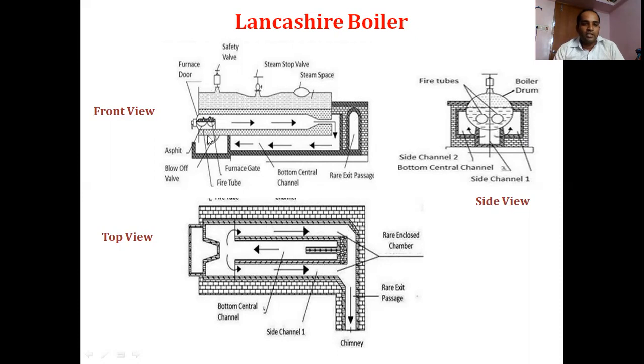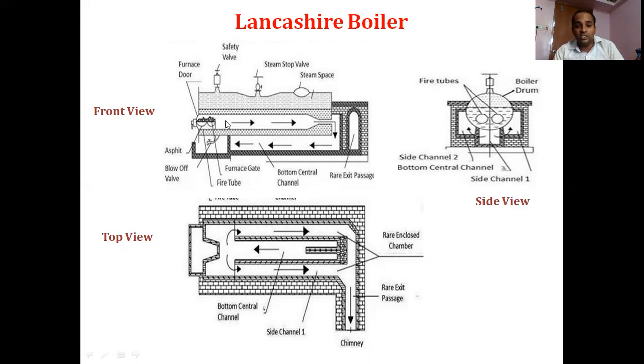Regarding the working of the Lancashire Boiler — it is a stationary boiler. It has two tubes, and within these tubes hot gases are circulated. So it is a fire tube boiler, where hot gases pass through the tubes and transfer their heat to the water present outside the tubes. The furnace is present inside the boiler shell, making it an internally fired, stationary, fire tube boiler.